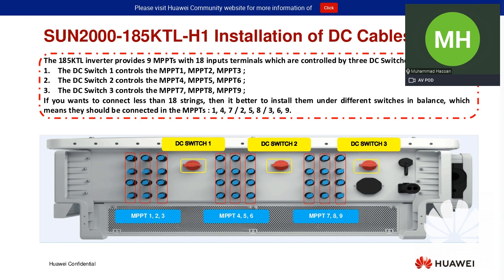Also, another important thing: this inverter comes with 18 inputs, and if you are planning to install fewer strings for this inverter, then we recommend you connect the DC strings in a format that will be balanced across all the DC switches. As I have mentioned here, if you want to connect fewer strings, they should be connected into 1, 4, and 7. That means one string in MPPT 1, the second string in MPPT 4, the third string in MPPT 7, and like that you will then increase the connections into the MPPTs. So it's always recommendable to use the strings in 147, 258, and 369 if you are planning to connect fewer strings to the inverter.